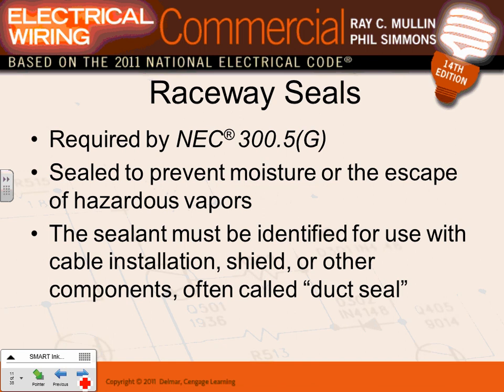Two types of seals: seal from outside to inside because of temperature difference, and seal from underground into the switchgear to prevent creatures - snakes and so forth - from getting into the conduit and into the switchgear, creating an arc flash hazard. There's also a third seal in hazardous locations - at gas stations, for example, you seal so the conduit doesn't channel gas from point A to point B in your system.